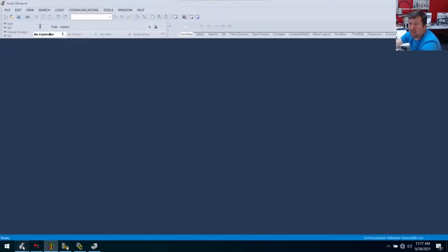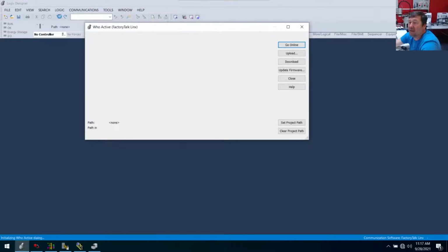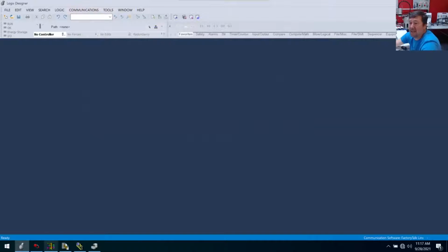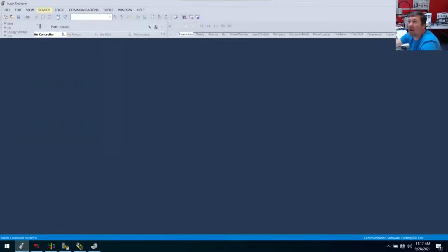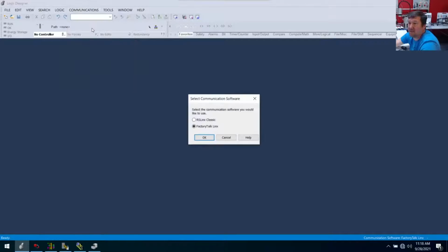But just to show what would happen if we had the wrong one, we're going to go here. And in Studio 5000, I always say go to Communications and then Who Active. Wait, I have to cancel this because I didn't talk about one thing. Since we have two softwares here, this is the old RSLinx, and this is the new FactoryTalk Linx, and our newer software gives you the option of which one to use. And if you're using Ethernet or USB, absolutely use FactoryTalk Linx. But right now we're going to go over serial because let's say we thought this was the right software. So we're going to select communication software, and I'm going to select RSLinx Classic.